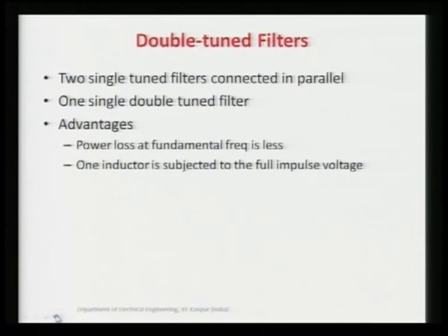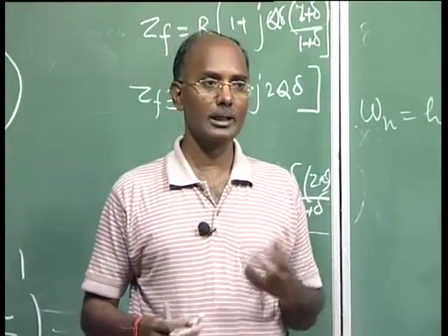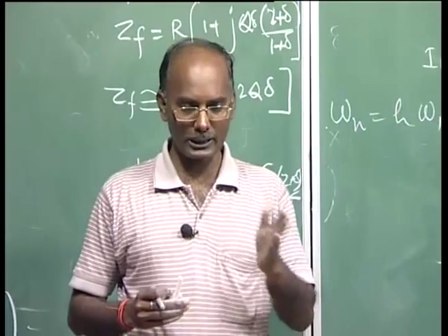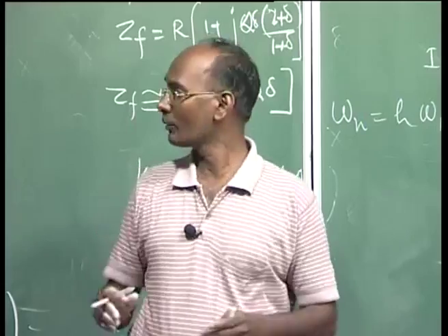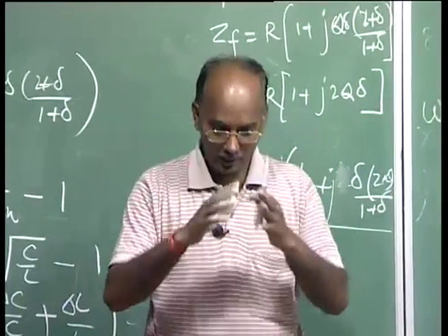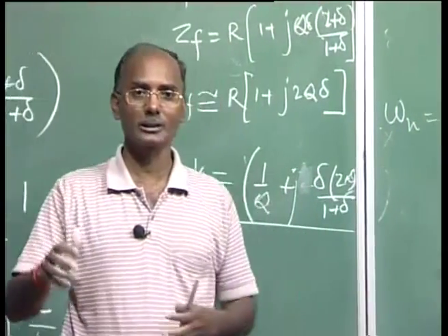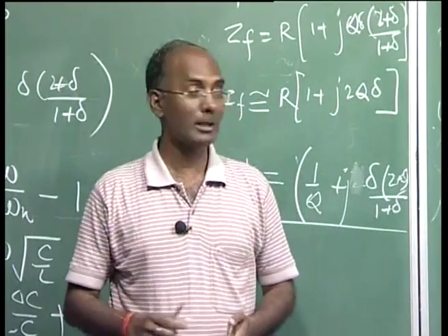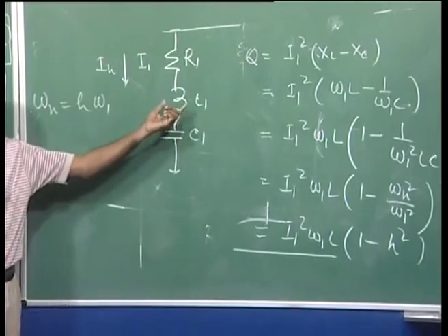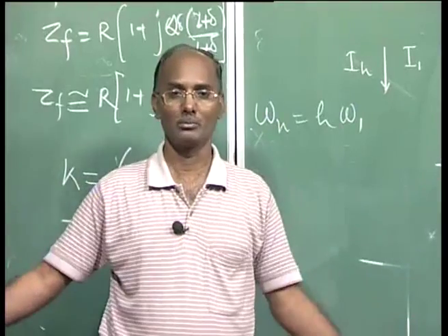So now another criterion is that we have to design the filter so that the cost should be minimum. Normally the cost of the filters is 5 to 10% of the terminal equipment. Terminal equipment, I mean the converter, all other auxiliary transformers, line, smoothing reactors, protection system, etc. The filters cost basically 5 to 7% of the total terminal equipment, because it looks like a very simple inductor and a very simple capacitor, but this capacitor requires use of this room.